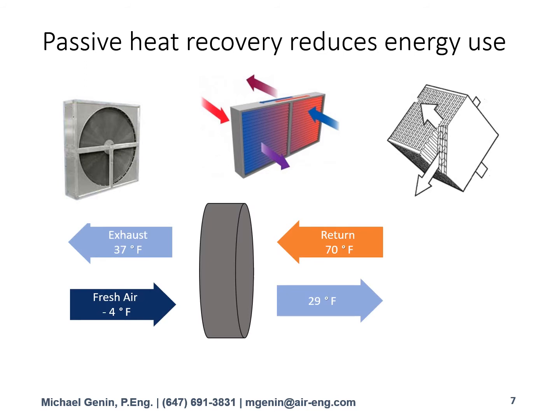So what ends up happening is, in this example, we're bringing our return air and we're bringing our supply air at -4 and running it through the heat rotor and achieving 29 degrees. And what happens in all these examples of passive heat recovery is we still need top-up energy. So in this case, for the same example of 11,000 CFM, we are burning now 500,000 BTUs of heat energy.